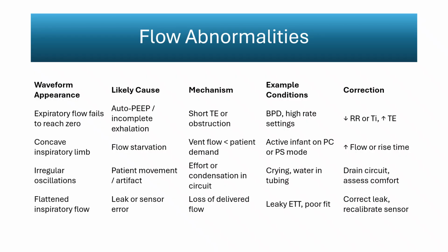Flow abnormalities provide some of the clearest clues about how the infant and ventilator are interacting. Each pattern reflects a distinct disruption in how gas moves through the airway or circuit. When expiratory flow fails to return to zero, the infant is not fully emptying before the next breath begins. This occurs with auto positive end expiratory pressure or incomplete exhalation. A short expiratory time or obstruction prevents the lung from reaching its resting volume, so flow remains above baseline. This pattern is common in bronchopulmonary dysplasia or when the ventilator rate is set too high. Correction involves reducing the ventilator rate or lengthening the inspiratory to expiratory ratio to provide additional time for passive recoil.